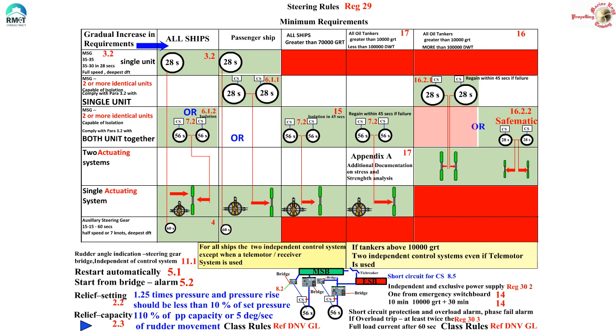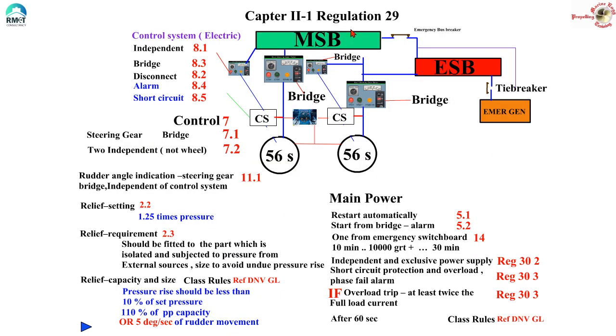Moving on to Regulation 29, Chapter 2-1 covers the requirements in detail about the steering gear. The main power circuit of the steering gear should be able to restart automatically after a power failure as per Regulation 29.5.1, and you should be able to start it from the bridge. Obviously you should also get alarms if power to the steering gear is lost.